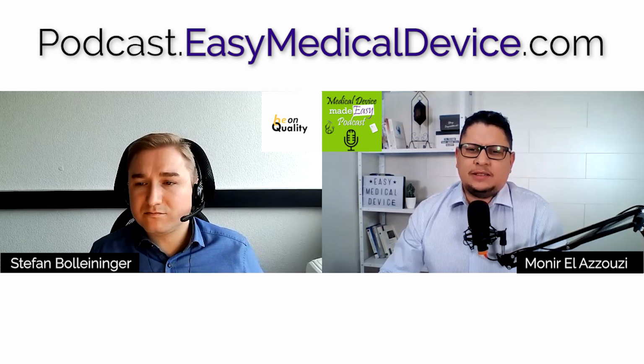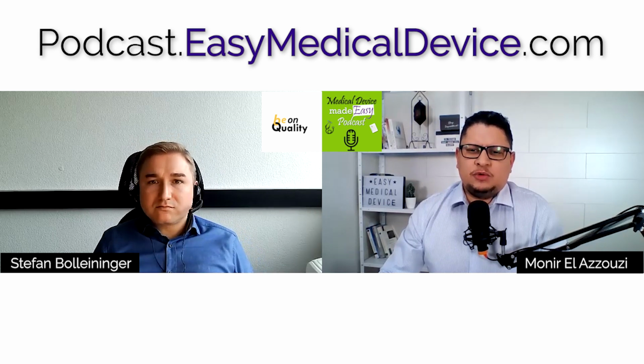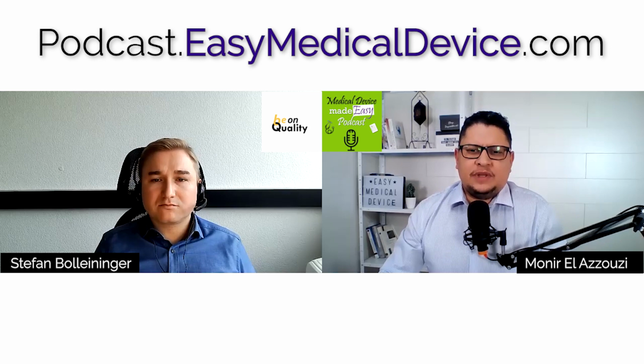So mainly we had the one that you are mentioning, the reuse of single-use devices. This is something that was mentioned in the EU MDR. There was an article, I can't remember the article number, specifically mentioning the possibility to reuse single-use devices. And they added to this, we call it a common specification, but as you mentioned, it's not specifically mentioned in the document that it is a common specification, which is number 2020/1207, if you want to go and look at it.